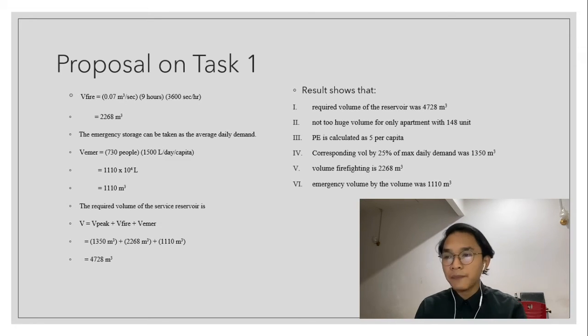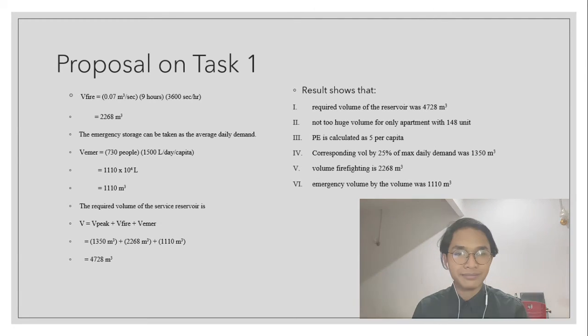Finally, the required volume for the reservoir is the sum of all the volumes: volume peak, volume firefighting, and volume emergency. So the total was 4,728 cubic meters. That's all from me for the calculation from task 1. Thank you.